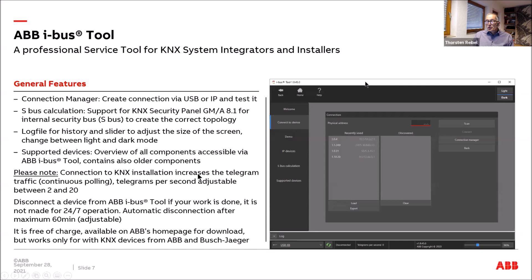An overview of supported devices is available and is continuously updated as new components arrive, while older ones are retained since they still exist in projects. When connected to a KNX device, additional telegram traffic occurs as the tool continuously polls components; you can adjust the polling rate between 2 and 20 telegrams per second. After finishing your work, please disconnect — after a maximum of 60 minutes, it disconnects automatically.